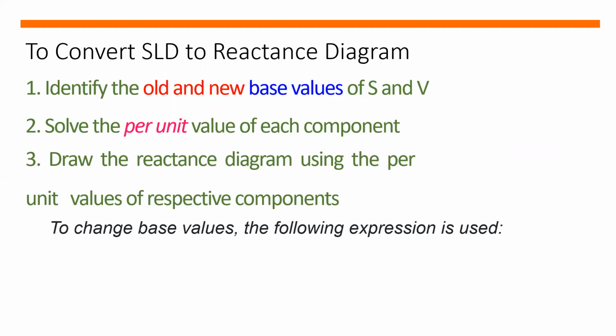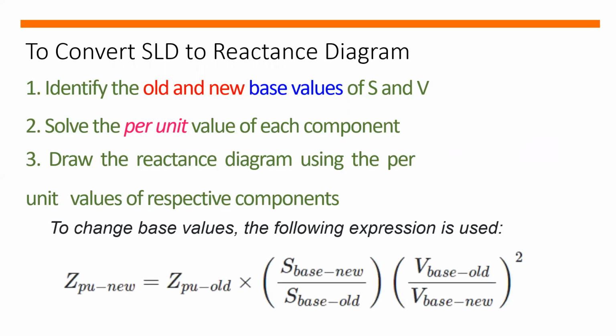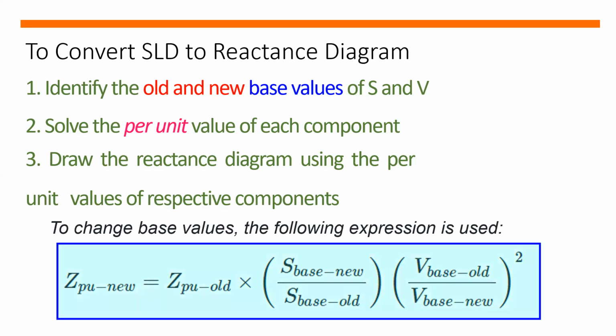So to change the base values, the following expression is used. The new per unit impedance is equals to old per unit impedance multiplied by the new base power divided by old base power multiplied by the square of the old base voltage divided by the new base voltage. So this will be our equation para makuha natin yung new per unit impedance.